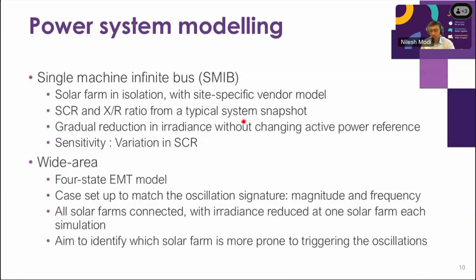In the SMIB analysis, the single machine infinite bus kind of setup, we looked at an individual solar farm, which we thought could be the cause of this oscillation in isolation. We used the site-specific vendor model, which was provided to us through the connection process. We looked at SCR and X/R ratio of a typical snapshot, to expose those IBRs to the typical SCR and X/R ratio they would likely see in real time. We applied a gradual reduction in irradiance without changing the active power set point, so it's just a slow change in the irradiance. We also did some sensitivity on variation in SCR of each of the solar farms. And we could easily see that there is a relationship between the irradiance change and the onset of oscillation.